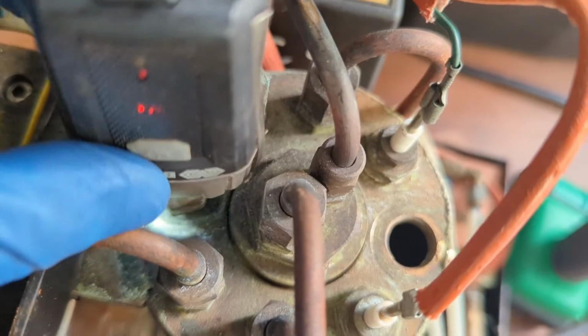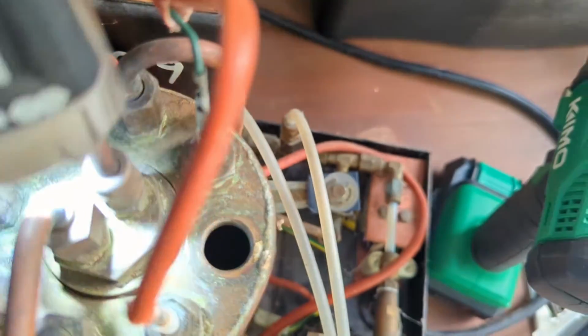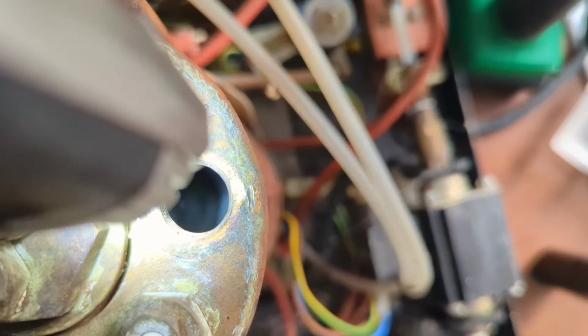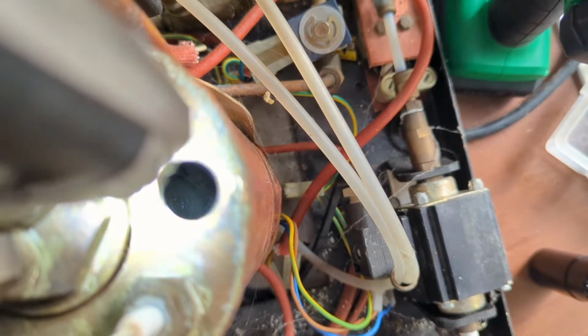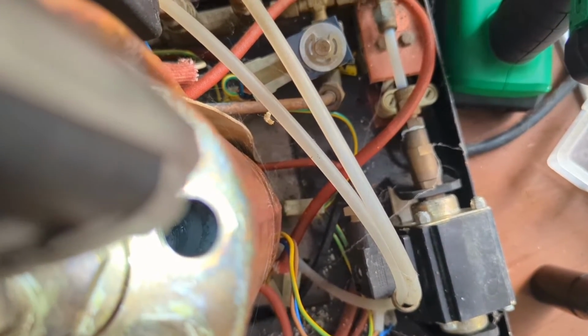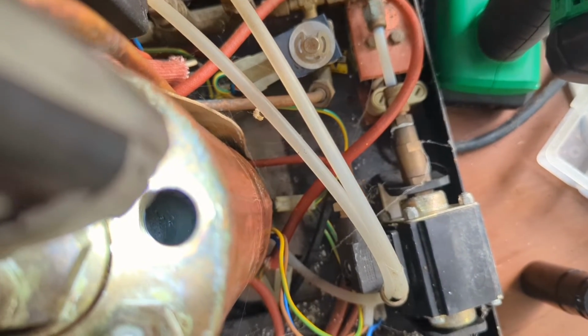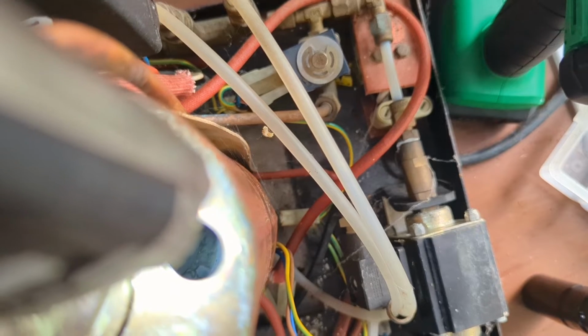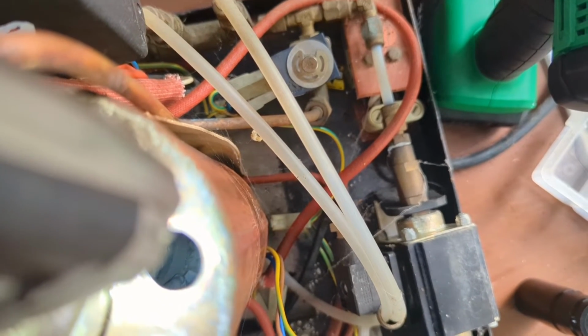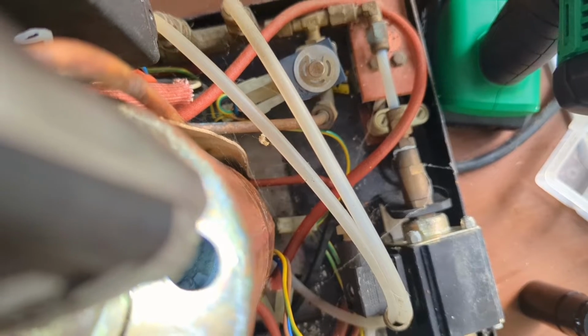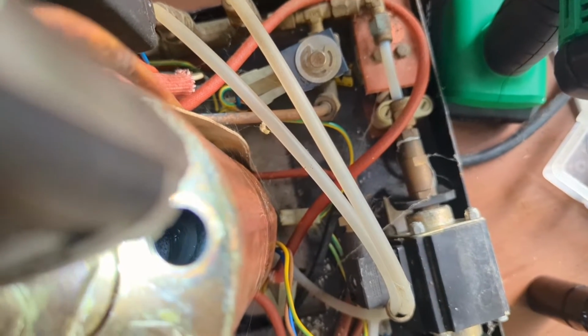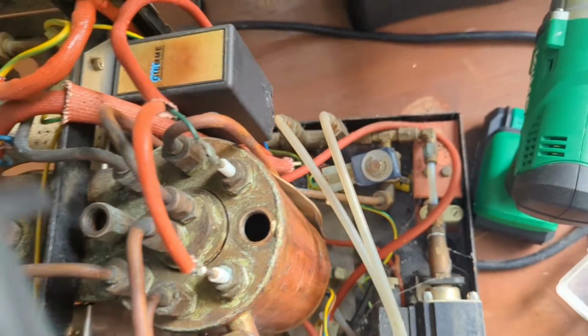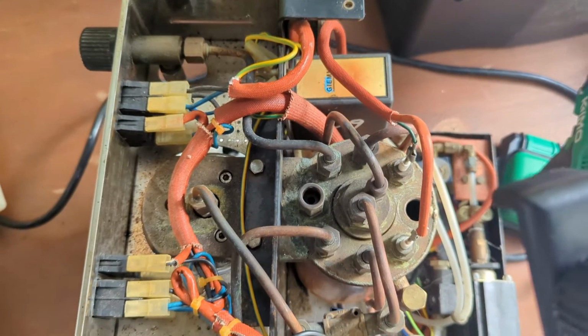Now, I'm not sure you can actually see the boiler inside. There you go. That's basically what you can see. So there's a little bit of scale buildup, as you see there. This is very hard to show on camera, but you see those little pieces out there, those white dots. Yeah, that's not good. That means that the scale buildup that we see on the vacuum release valve is all over the inside of the boiler. So yeah, we're gonna have to descale the whole thing and take it all apart.